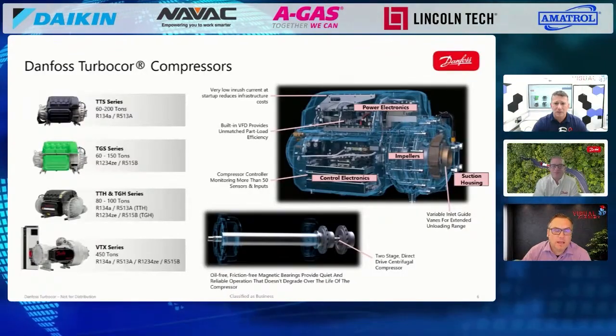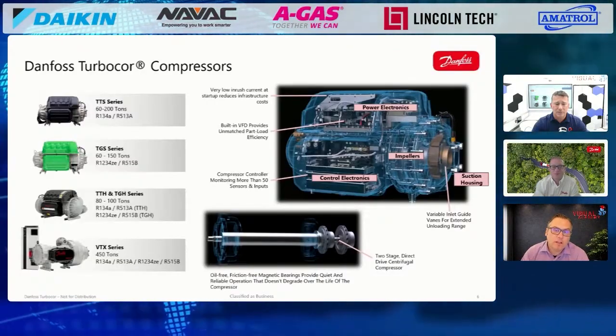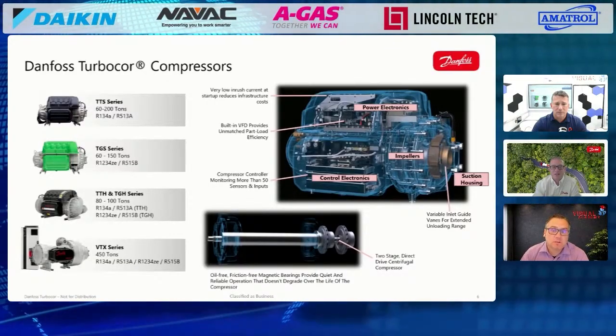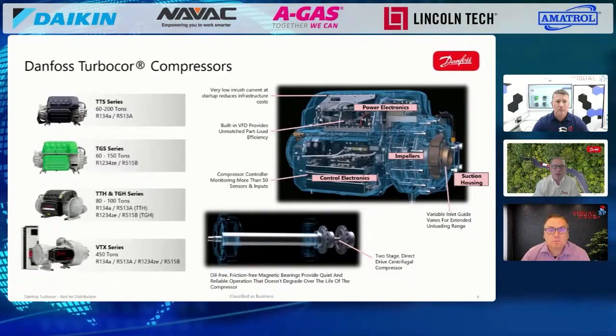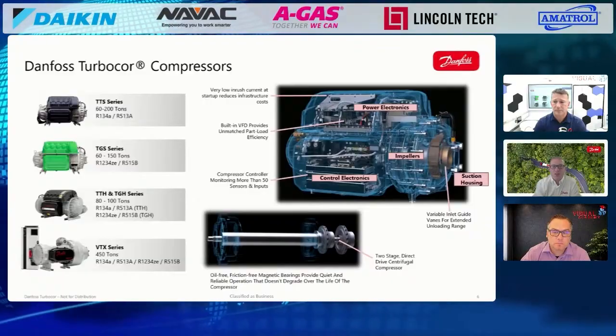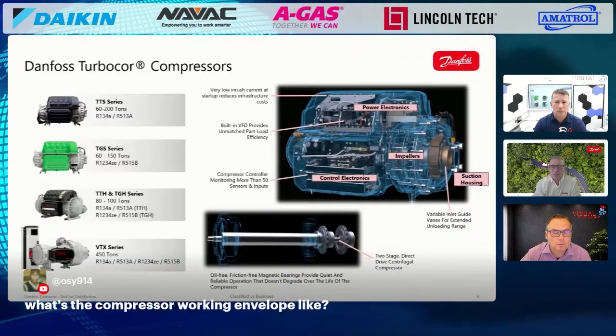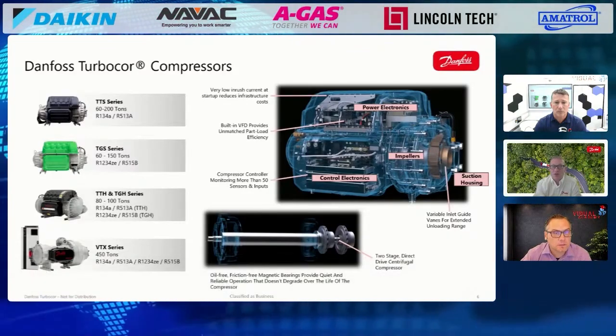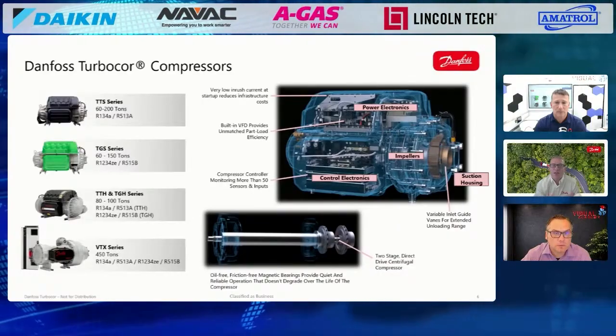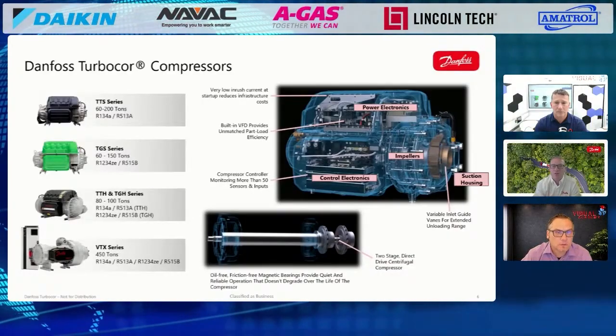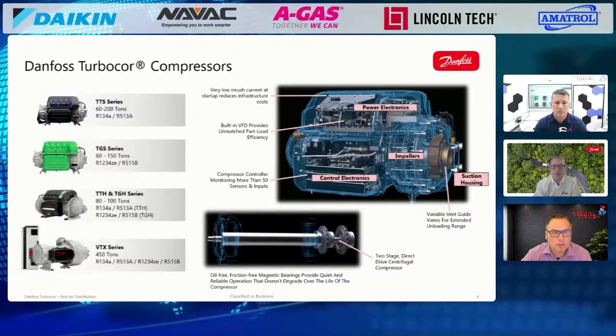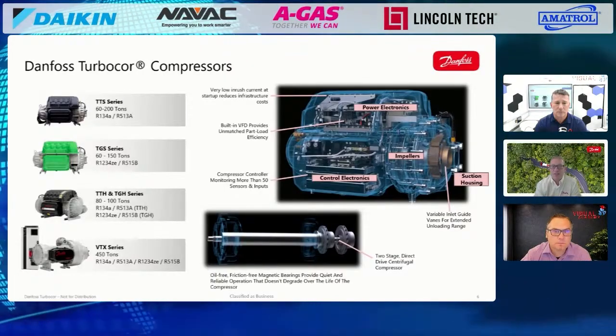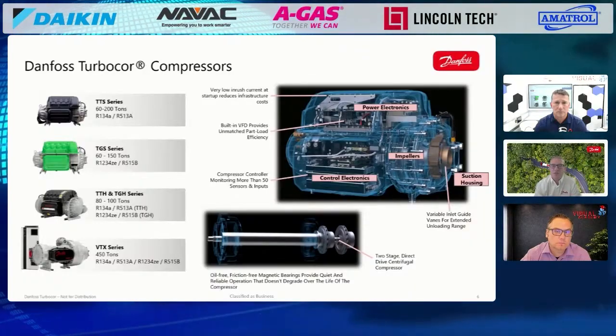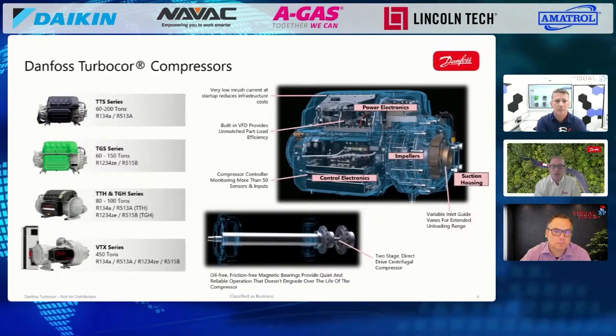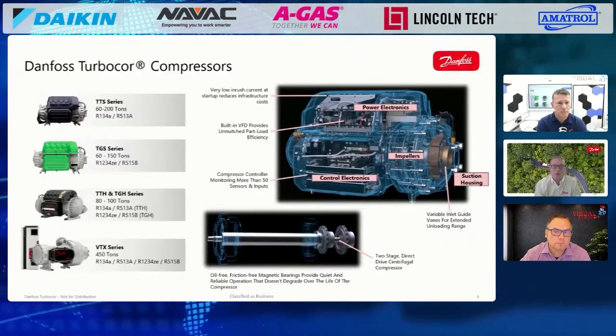Now on this slide, are these the 4 different variants? Are there other variants, smaller ones for much smaller systems? Yeah, so these are the 4 main models. Even the first two, the TTS series and the TGS series, are basically sister compressors—the change is in the refrigerant. The TTS series is for the traditional R134A and its newer lower GWP replacement R513A. The TGS series is the same compressor, same aero design, but for different models using 1234ZE and 515B—the ultra low GWP refrigerants of the future.